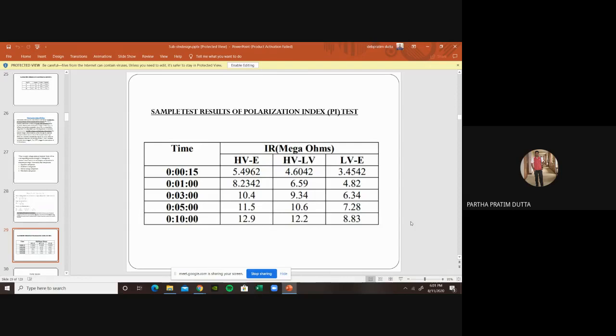Now, if you divide these two, 12.9 by 8.23, it is always greater than 1. 12.2 by 6.59, it is also much greater than 1. That is, the insulation is very good. And 8.83 by 4.82 is almost close to 2. That is, the insulation is very good. In that way, by the polarization index test, we measure whether the insulation is perfect or not.